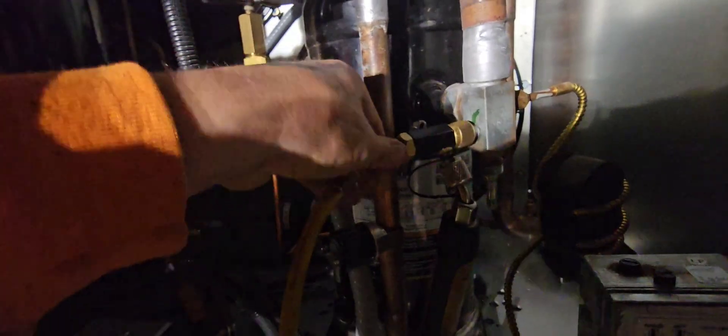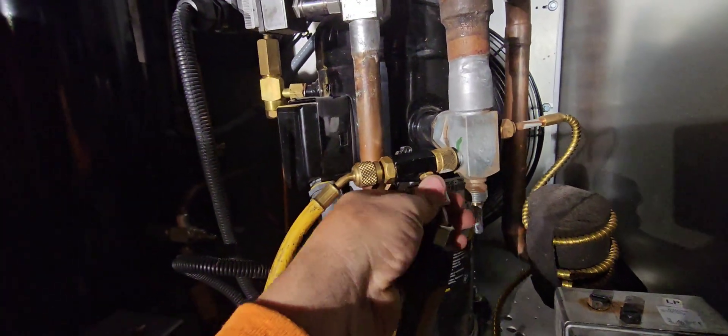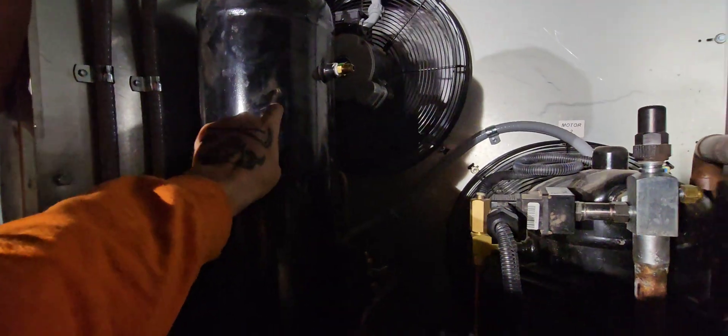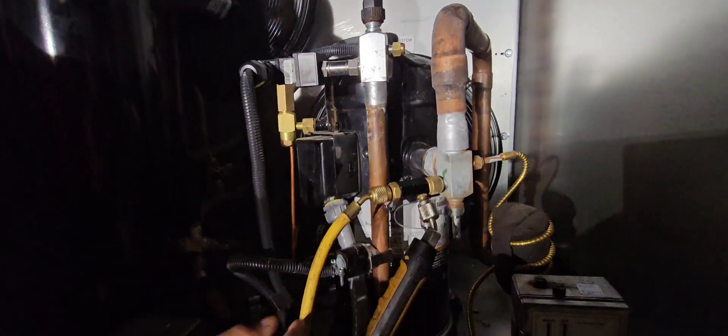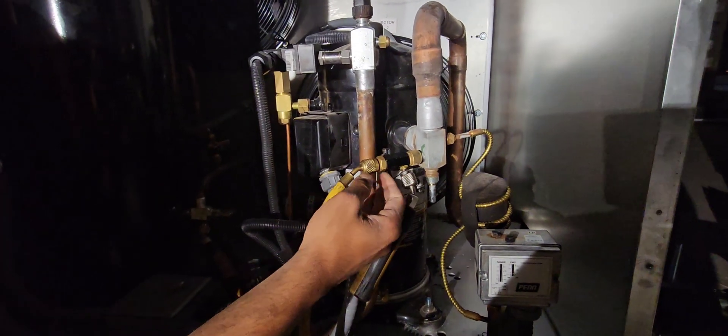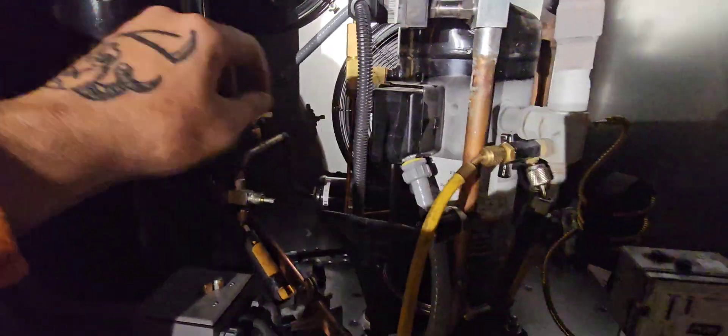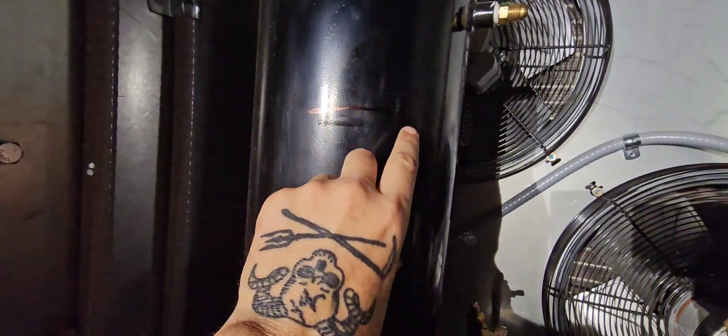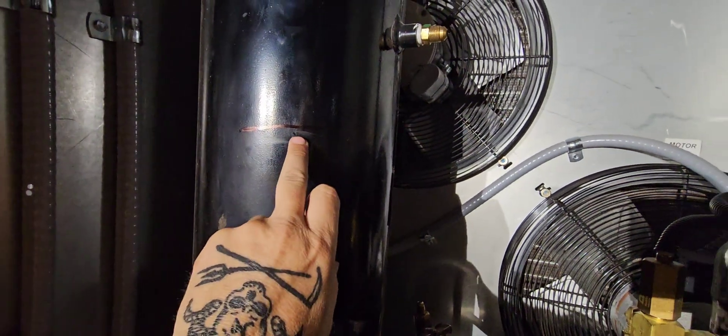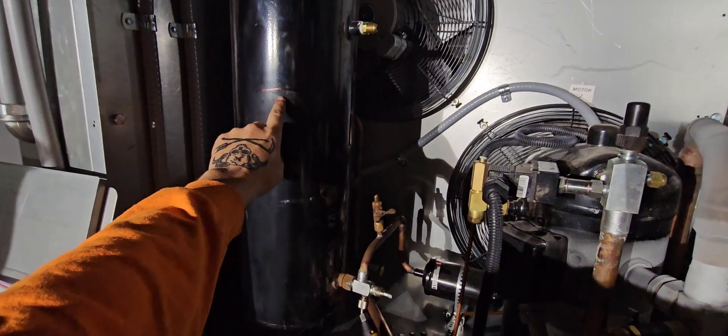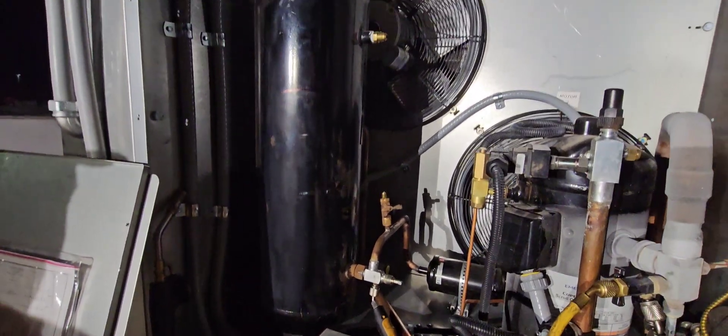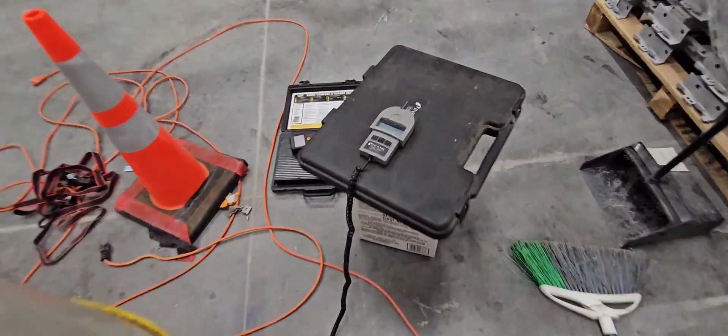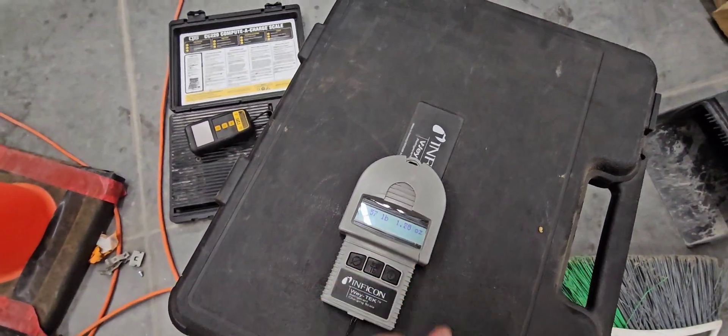We're just going to let it go until we get to about 80% receiver. Once we're at 80% that's the max charge the system can take. We'll plug that solenoid back in and let it run but for right now we're just going to charge this thing up. We got this thing all charged up. You see you're pushing a little liquid in there. Marked it right here with my sharpie. Usually I have a paint pen. I'll have to get a paint pen on it, but we got it about right there. It's pretty decent receiver level. So all we got to do now is just go back downstairs, hook up that solenoid and let it run, watch it come down to temp. Let's see how much, so we took 57 pounds.